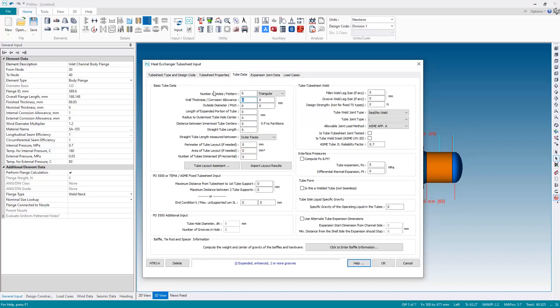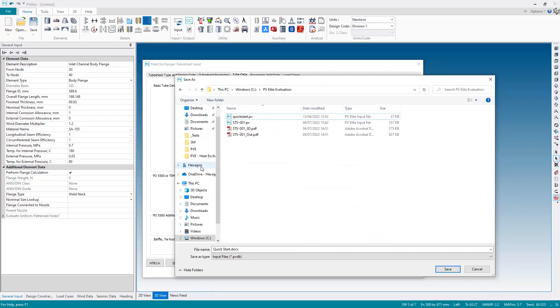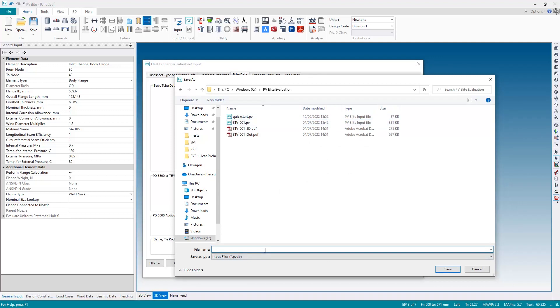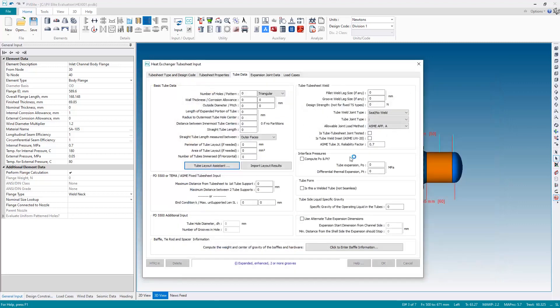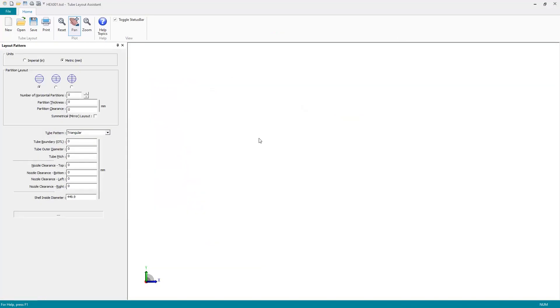So I need to specify the number of tubes and the tube layout, which I can do here. I can specify the number of holes and so forth in the tube sheet. Or alternatively, PVLite can assist me with this using the tube layout assistant, which is what I'm going to use here. So I'm going to hit tube layout assistant and accessing the tube layout system does require me to save the file. So I'm just going to give this a name. I'll just call it heat exchanger one and save it into a suitable location. Upon doing that, the tube layout assistant will appear here.